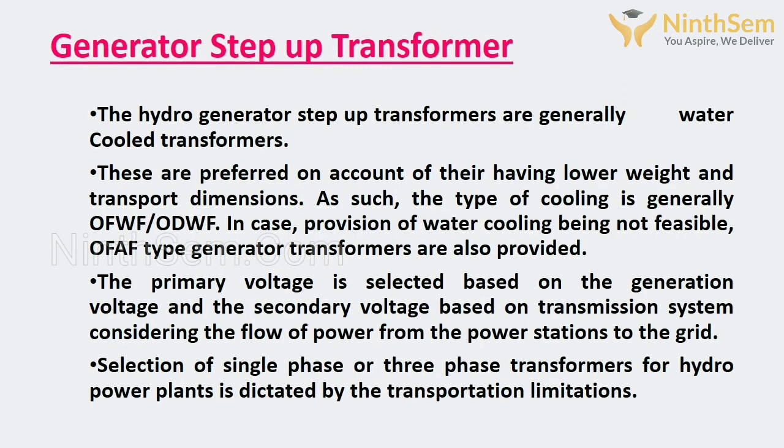Generator step-up transformer. The hydro generator step-up transformers are generally water-cooled transformers. These are preferred on account of having lower weight and transport dimensions. As such, the type of cooling is generally OFWF or ODWF. In case provision of water cooling is not feasible, OFAF type generator transformers are provided.